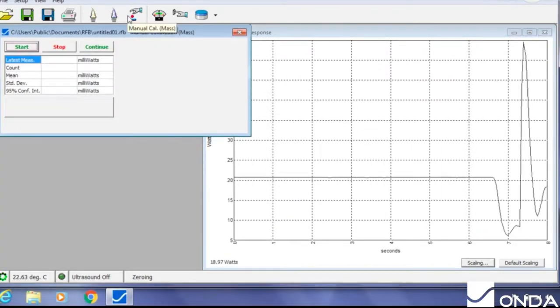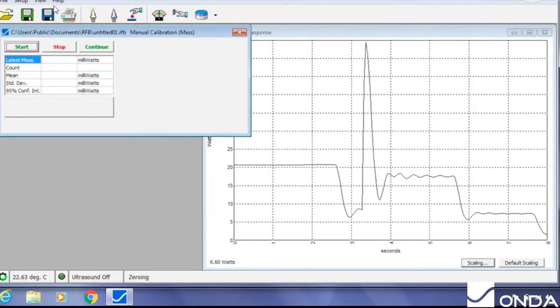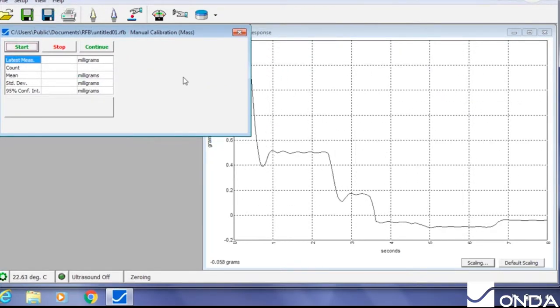After entering the known weight of the calibration reference mass when prompted, press OK to read and acknowledge the instructions.